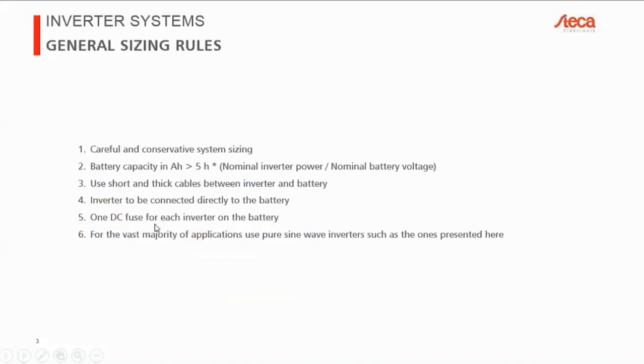So that's the fourth rule. The fifth one is we need one DC fuse for each inverter on the battery. Of course, you can use two fuses, one in the positive and the negative, but the minimum is one. It's important to use a fuse separately for each inverter for a couple of reasons. One reason is, of course, if you're using several inverters, and if you're using one fuse for all inverters and that fuse blows, well, then you've turned off your entire system, so you have absolutely no redundancy at all.